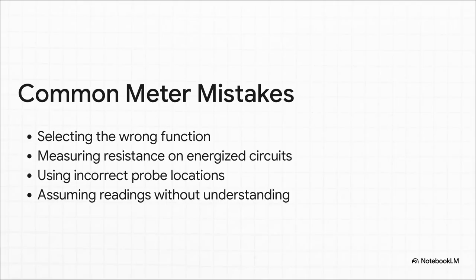But look, the meter is only as smart as the tech holding it. You've got to avoid those common rookie mistakes, like selecting the wrong function or using incorrect probe locations. And most importantly, this is critically important: never ever measure resistance on a live energized circuit, unless you actually want to fry your equipment.